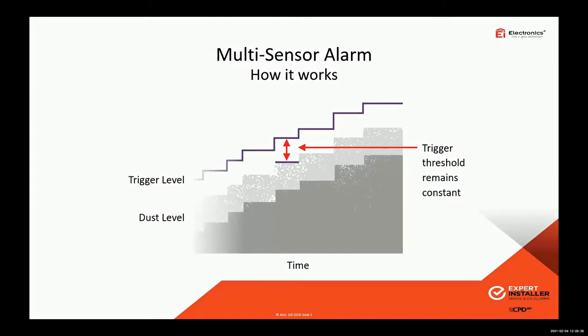We have what we call dust compensation built into this unit. Dust can be a major issue from the smoke detection point of view because the chambers in smoke detectors rarely differentiate between smoke and dust. It's still an obscuration level within the chamber itself. But we have put dust compensation into these devices. Basically you have a basic dust level, or basic thresholds, within the unit, and that threshold has to be maintained as a constant. If you get a dust buildup, then the thresholds would get closer together, and that sets the unit into false alarm. But what we have done here is use a step-up situation which happens 32 times over the life of the unit. So if you do get a buildup of dust in the bottom threshold, the top threshold actually moves at the same rate. So that constant is maintained over the life of the unit. That's a massive advantage as well.